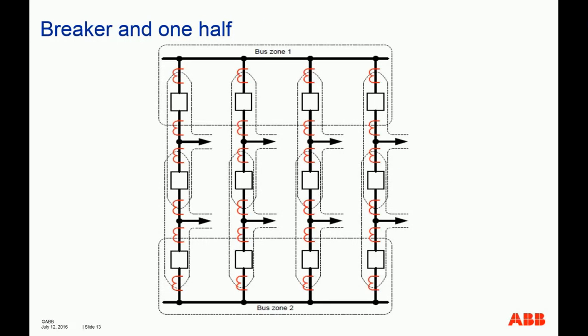Breaker and half, we see this probably most often for high voltage or extra high voltage substations, especially for transmission stations, on the switch yard of a big generation plant. Because they have three breakers and two feeders, we typically call it breaker and half, because each feeder is actually protected by 1.5 breakers, 3 divided by 2. So again, this type of configuration also allows you to take any bus out of service for repair or maintenance, while not disrupting the operation of the load.